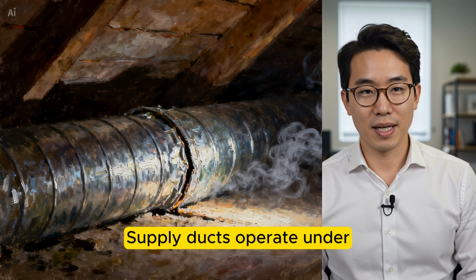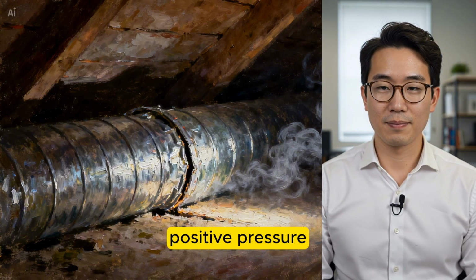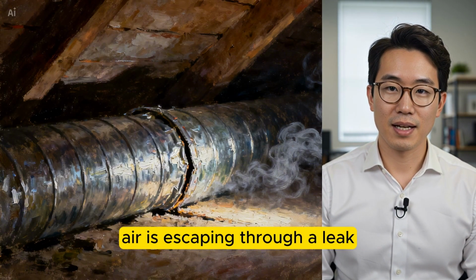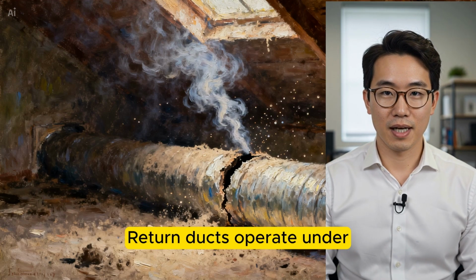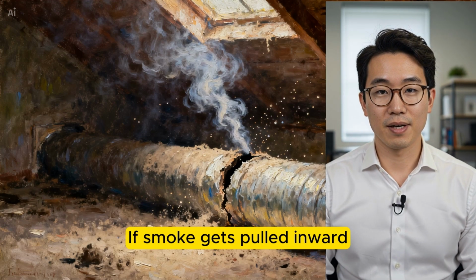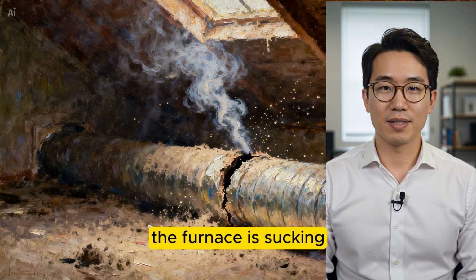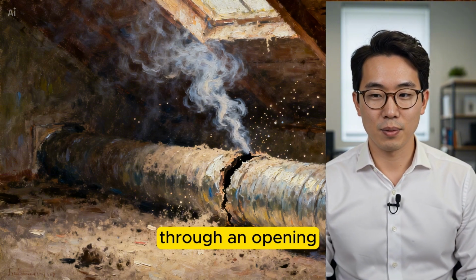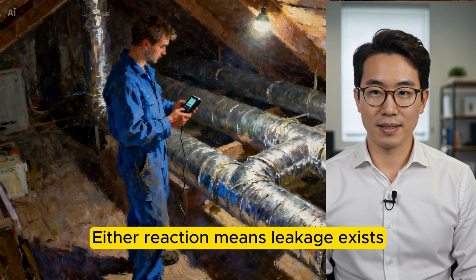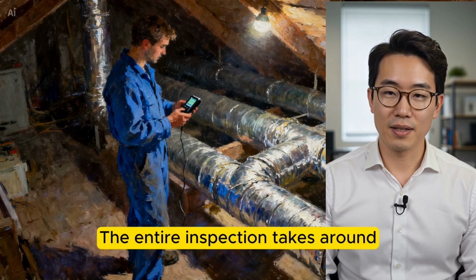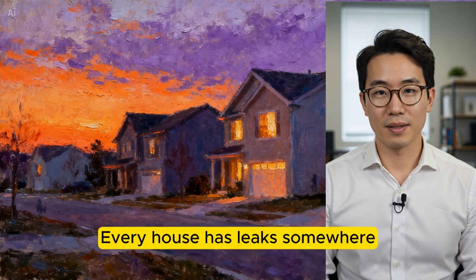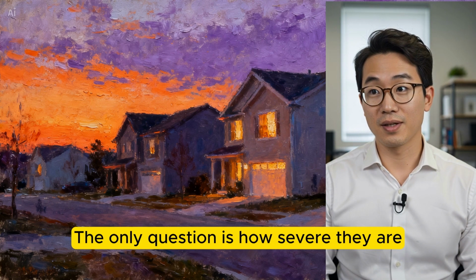Supply ducts operate under positive pressure. If smoke blows away from the joint, conditioned air is escaping through a leak. Return ducts operate under negative pressure. If smoke gets pulled inward, the furnace is sucking attic air back into the system through an opening. Either reaction means leakage exists. The entire inspection takes around 15 minutes. Every house has leaks somewhere. The only question is how severe they are.